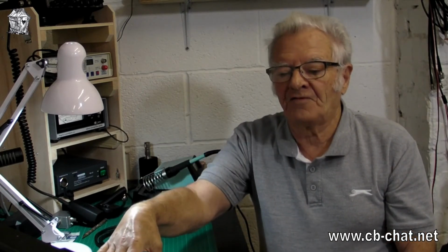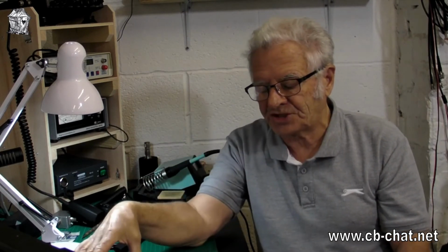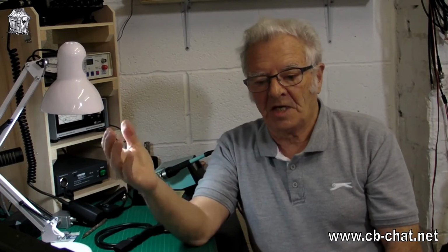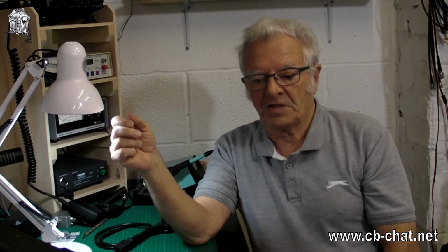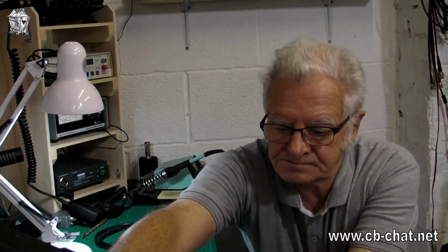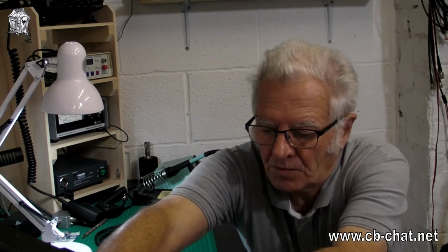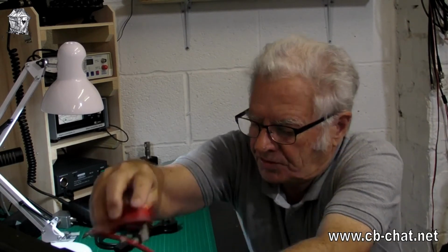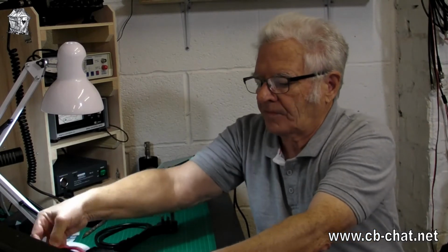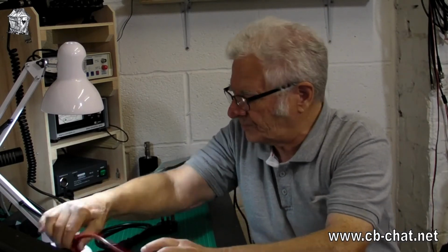So we know that it's working, it's doing its job, because it detected a faulty low insulation, which is what this box simulates, and it's failed. So we've tested that. Okay, now take that out and we'll test something else.